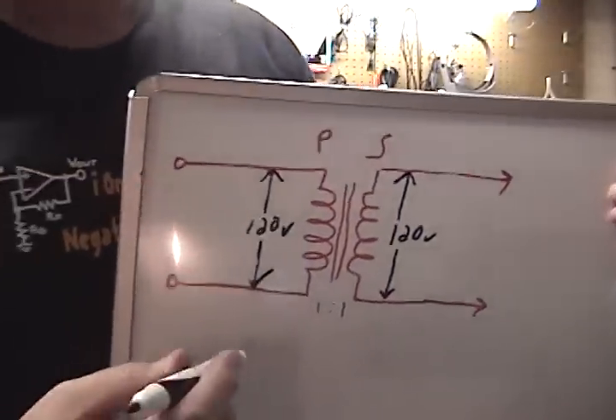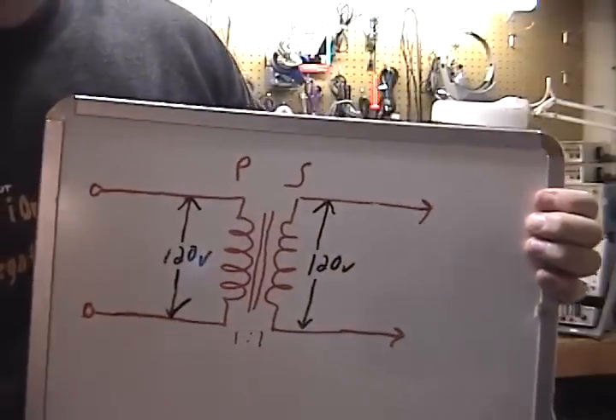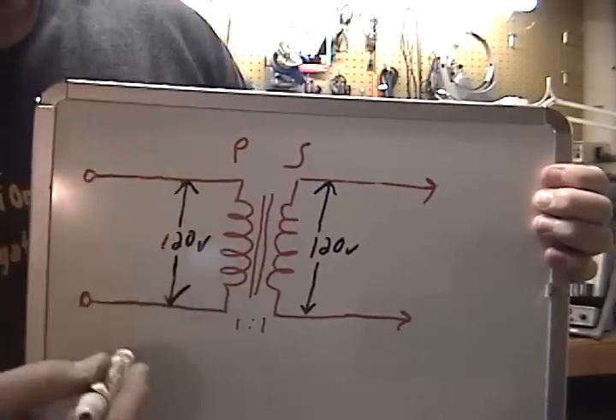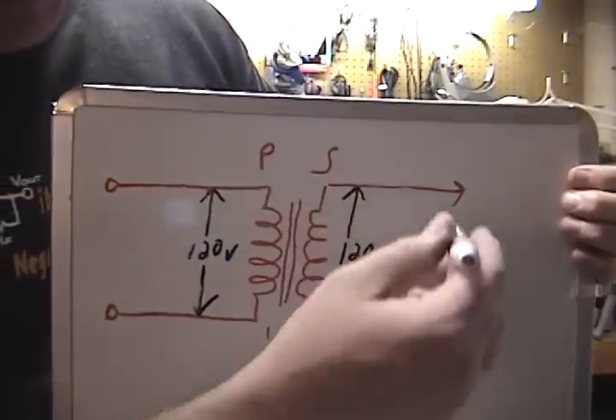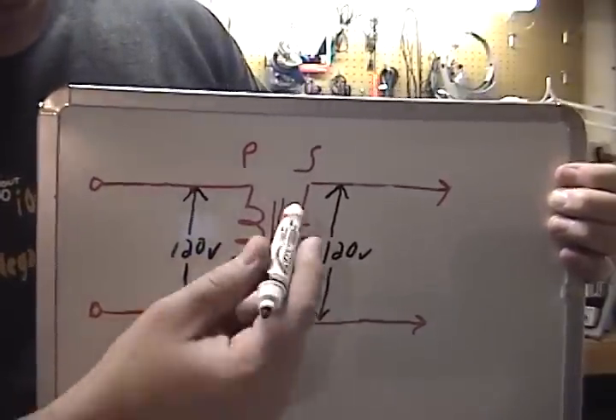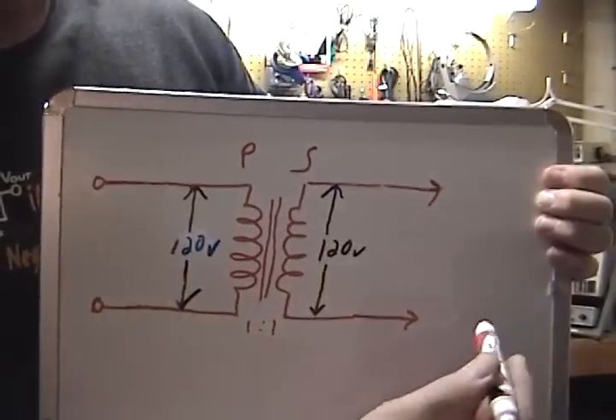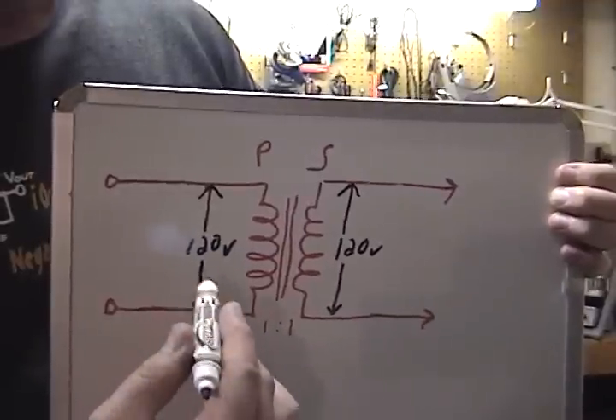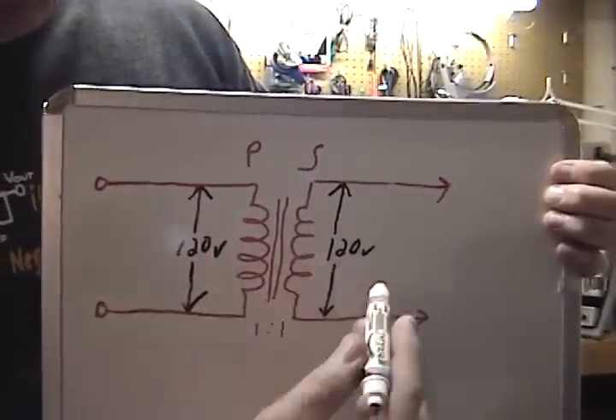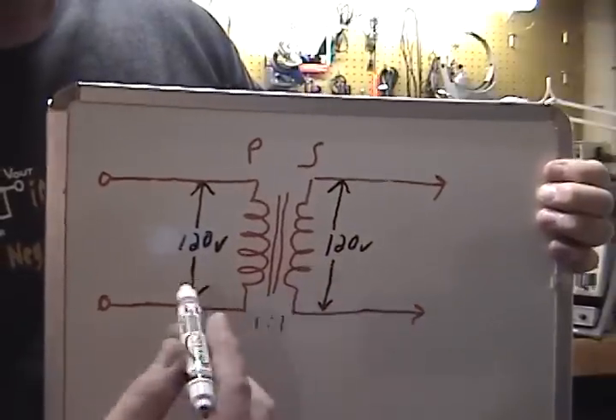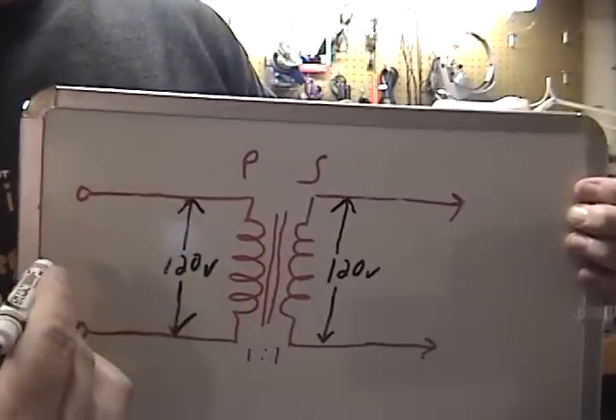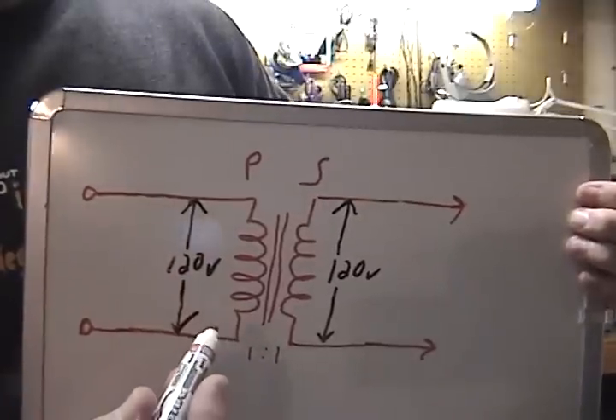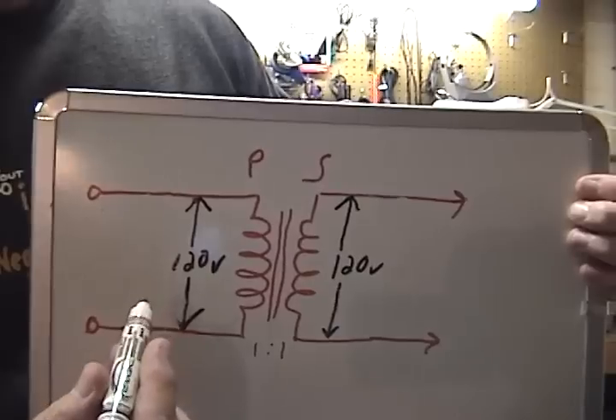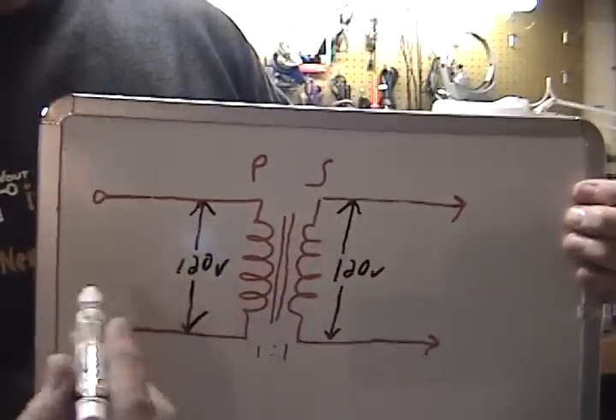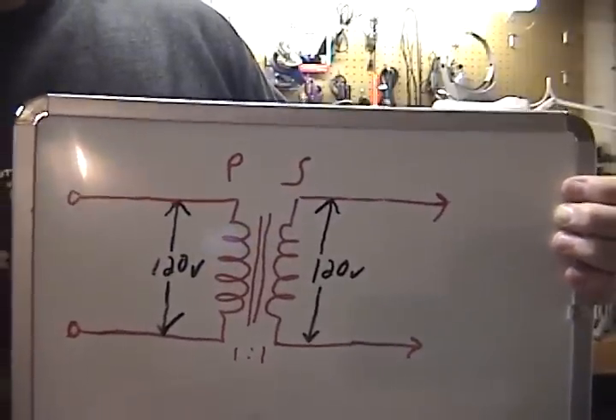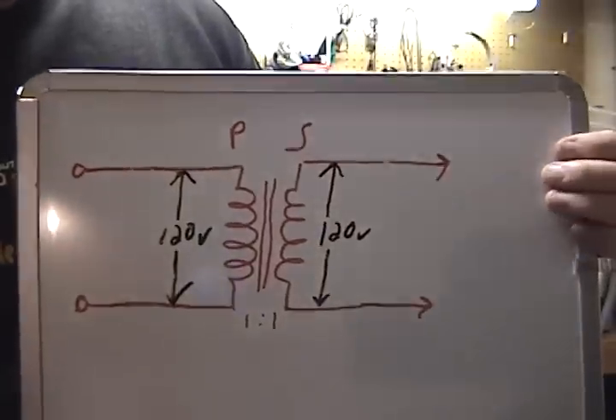So just to make it simple on the diagram here, I'm showing an isolation transformer. It's essentially any transformer. You have a primary, P, over here, and then you have your secondary, S, over here. Because it's a 1-for-1 transformer, the coils are exactly identical, and if you have a load over here, the voltage of 120 volts here, because of transformer theory, will show up on this side exactly the same, 1-for-1, 120 volts. But because of the way transformers work, spikes, like say if a motor turns on or off someplace in your building and a spike goes on the line, that's an instantaneous change that can't go across this transformer.